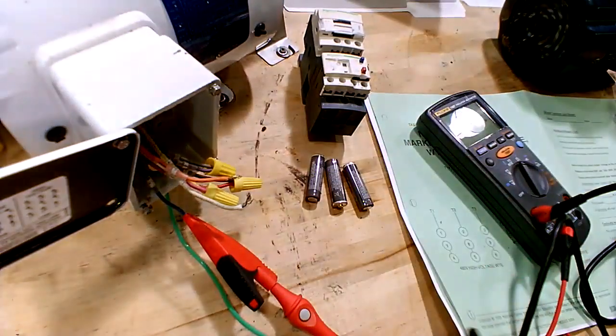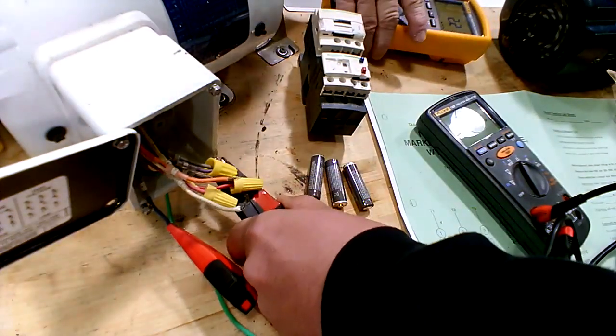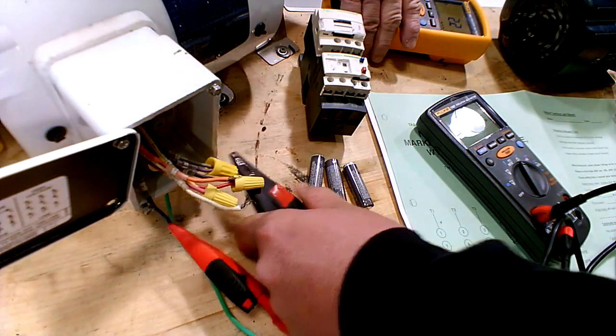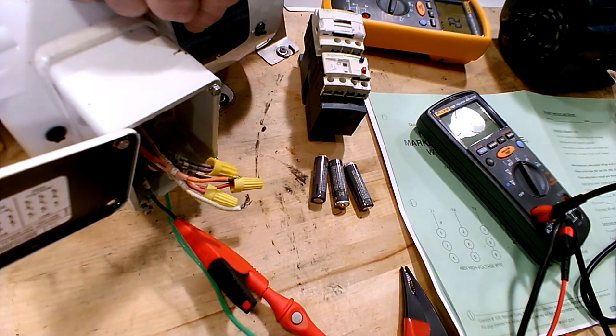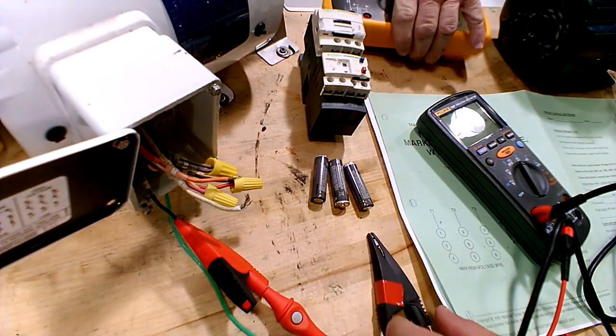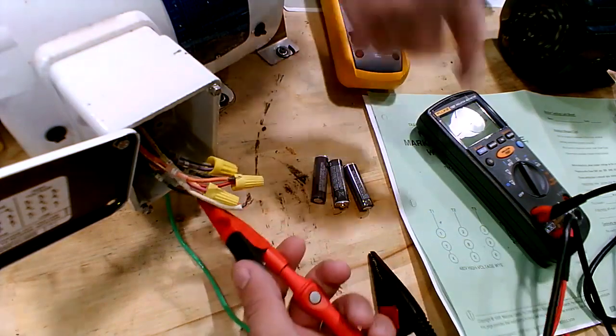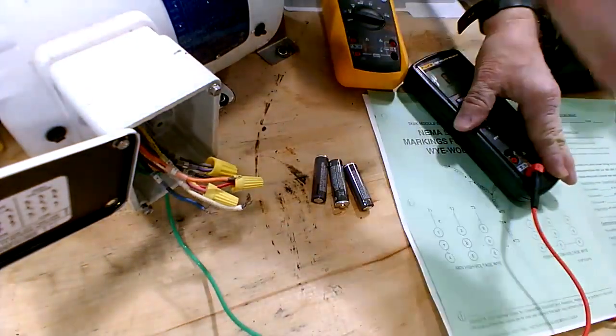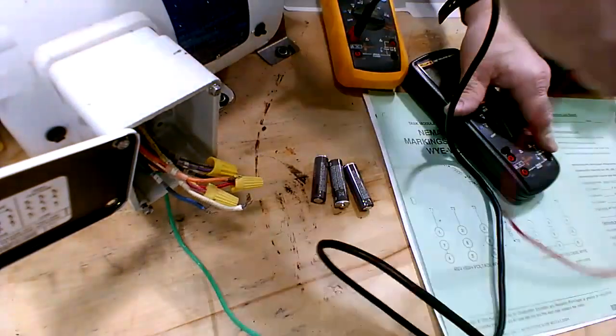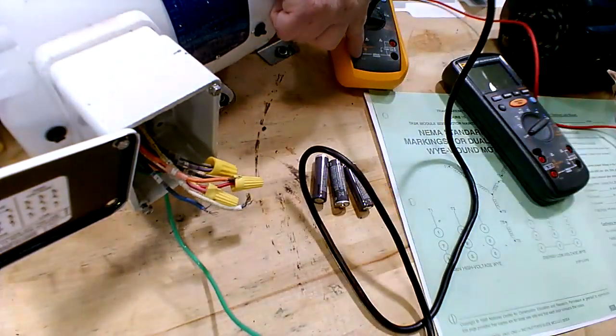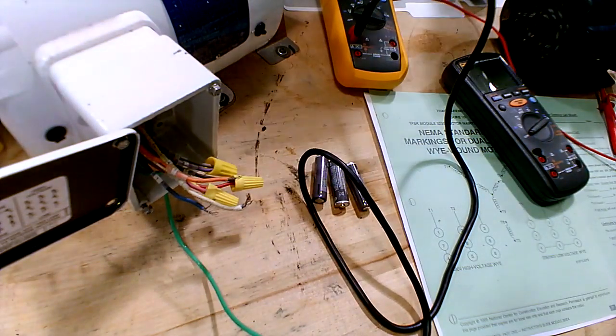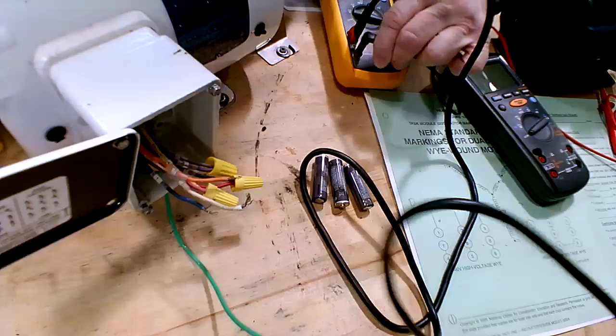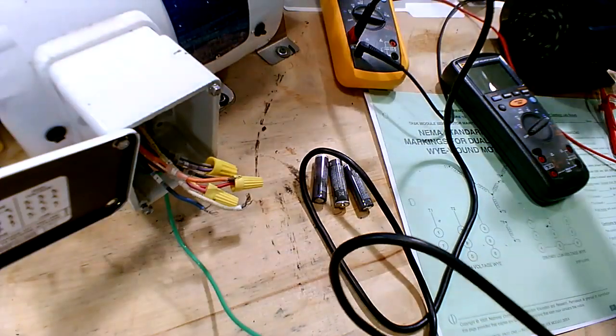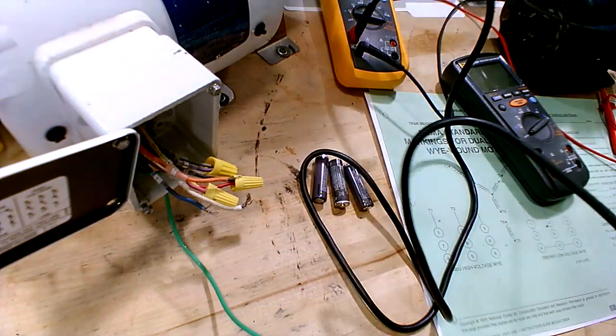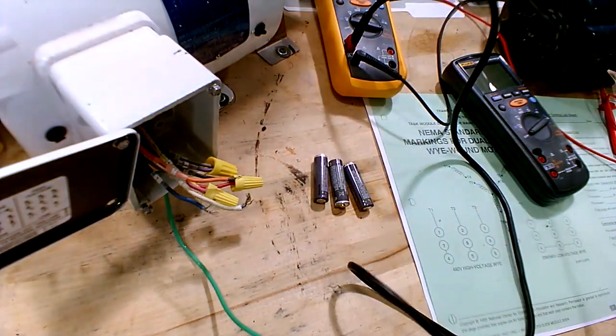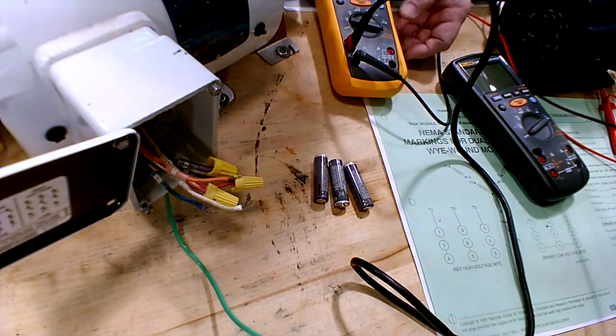It's not there. You're not going to read it. No, you don't do it that way. As far as did y'all do the readings through the motor? We're trying to make it better. Okay, let's back up. Let's do the insulation test first. Okay, let's plug this into here, and then the common lead goes into here. Where is that? Let's get the clip. Even though it's showing a battery symbol, it will actually do it, and we're not going to put batteries in there.